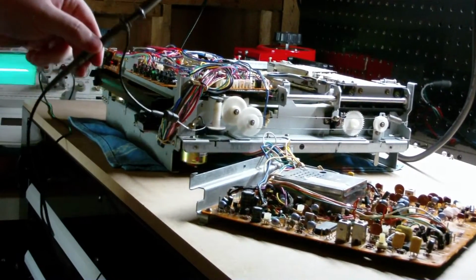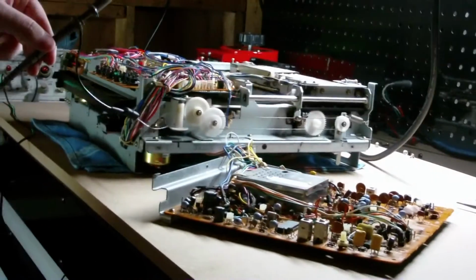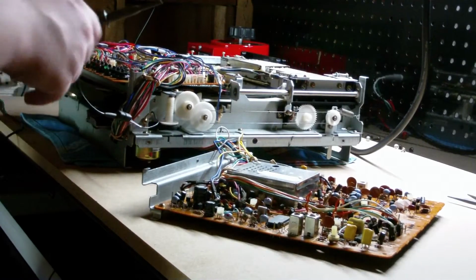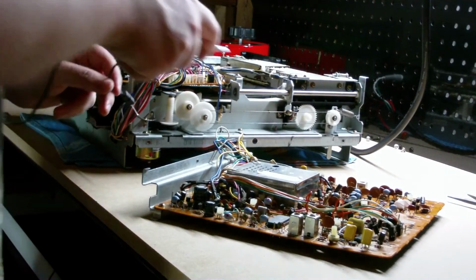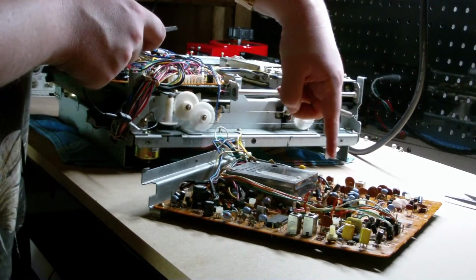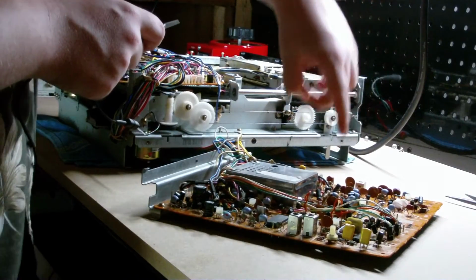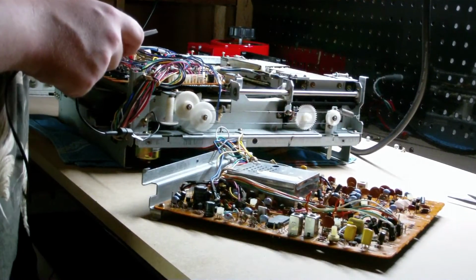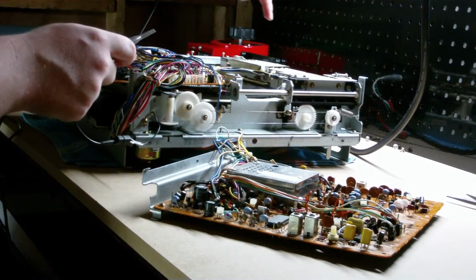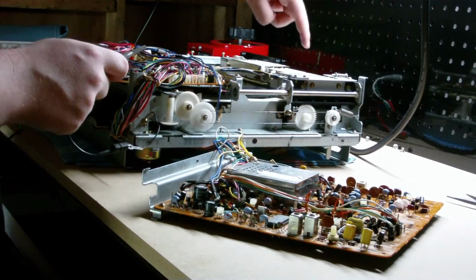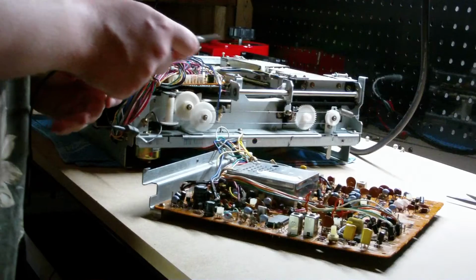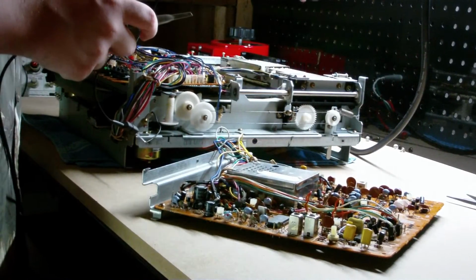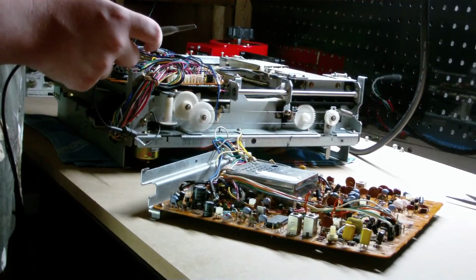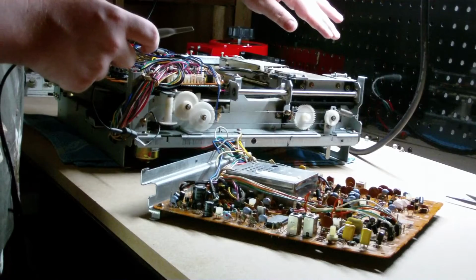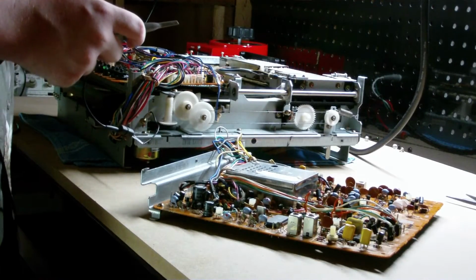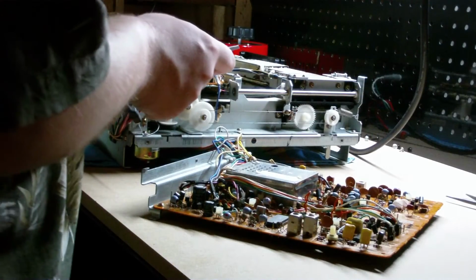This is going to be a bit of a balancing act. I can always just go over to my probe screen. So test point 101 is here. This confirms there is an output from the stylus arm. Yeah, there's my finger. No output from the stylus arm would mean a bad arm, and we have to look there to see where we could possibly perform component level repair on the arm preamp. Difficult to do, but it can be done. And if the resonator were bad, then you need to replace the arm as a whole. There's no way to repair the resonator.